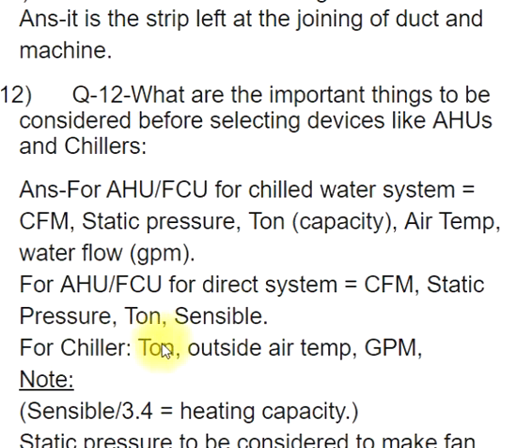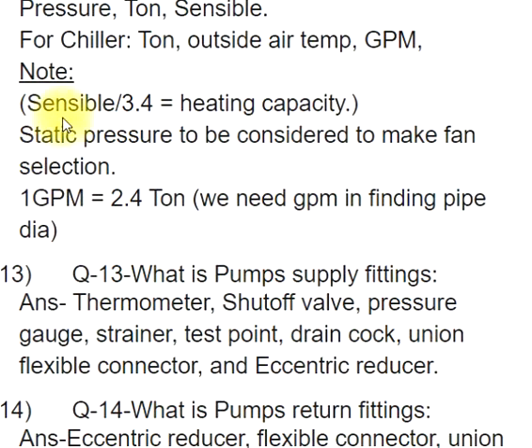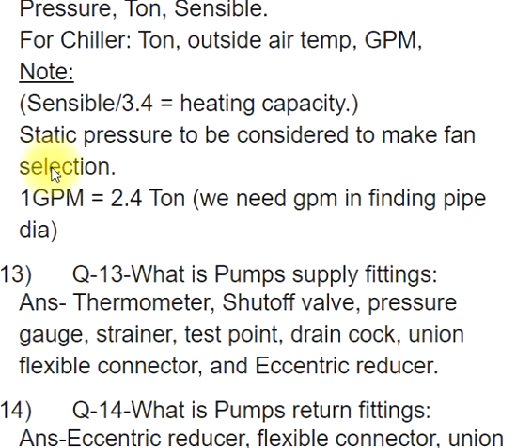Note: Sensible / 3.4 equals heating capacity. Static pressure to be considered to make fan selection. GPM equals 2.4 × ton; we need GPM in finding pipe diameter.